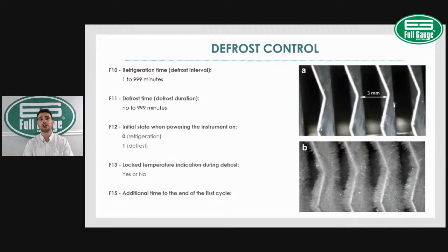Sometimes you get a call from your customer, like we spoke before, saying, hey, my cooler is not working, my temperature is too warm, and the system is under defrost. So by locking the last temperature reading before defrost, you can actually prevent those false service calls.